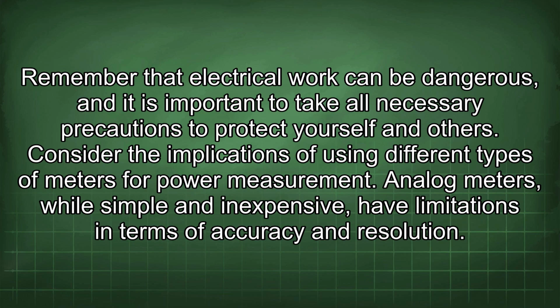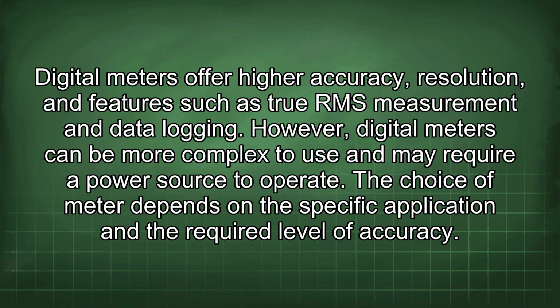Consider the implications of using different types of meters for power measurement. Analog meters, while simple and inexpensive, have limitations in terms of accuracy and resolution. Digital meters offer higher accuracy, resolution, and features such as true RMS measurement and data logging. However, digital meters can be more complex to use and may require a power source to operate. The choice of meter depends on the specific application and the required level of accuracy.